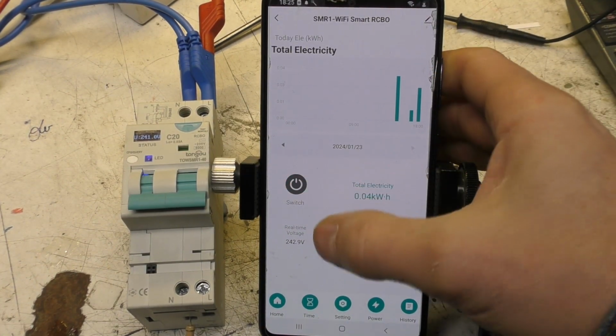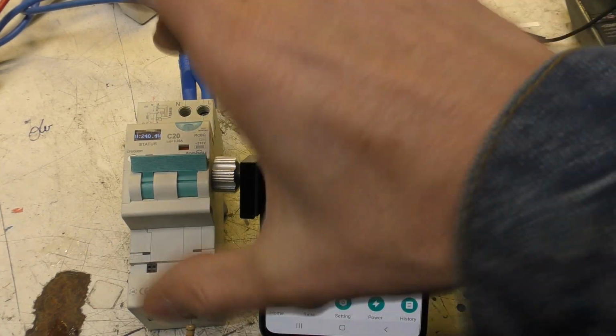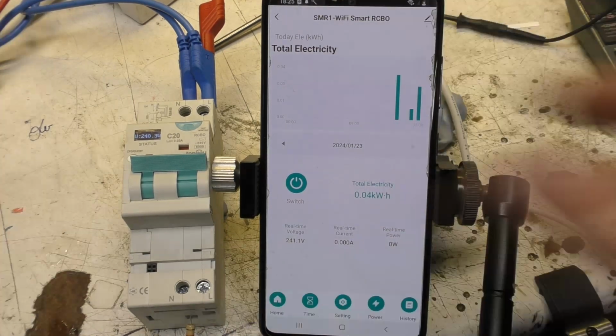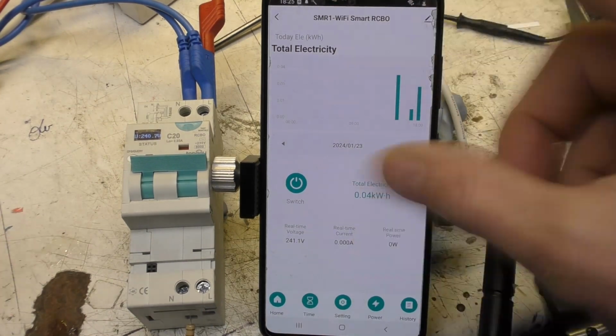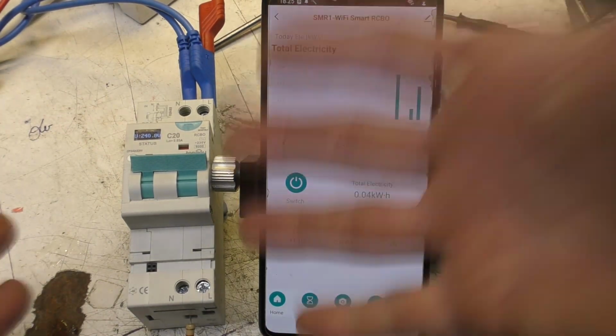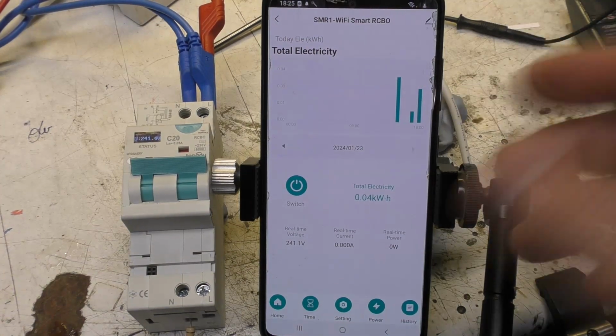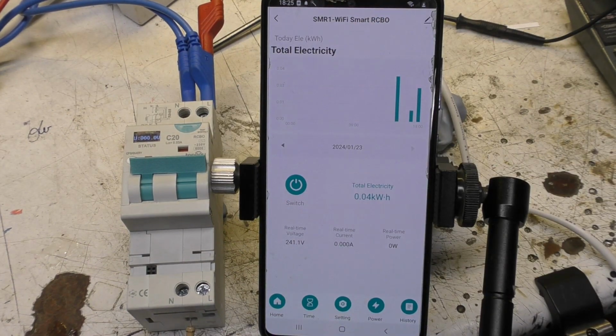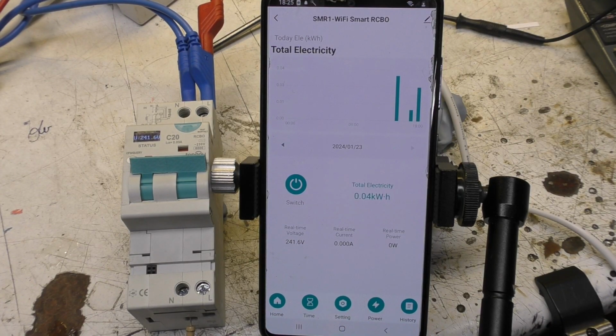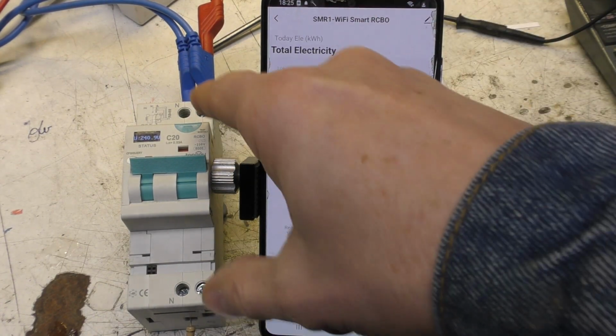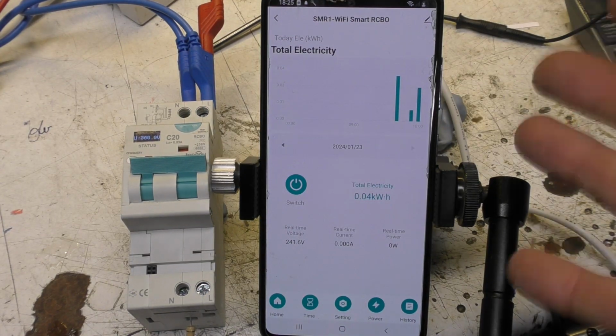It's just absolutely crazy. Something which did everything that this claims to do, but in a different type of package, or something which is very clearly labelled that says this is not a primary overcurrent protection device. A situation I can see where this might be useful is, for example, where you've got a temporary setup, and you've got temporary power being provided, let's say for an event. If you've got one of these, obviously you need to have the proper upstream protection.